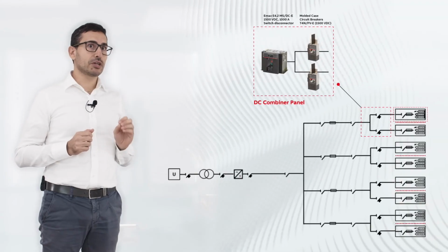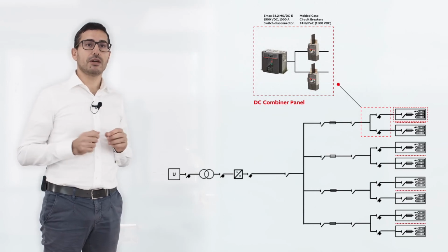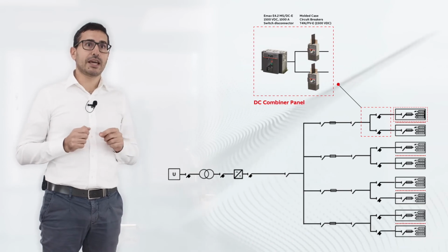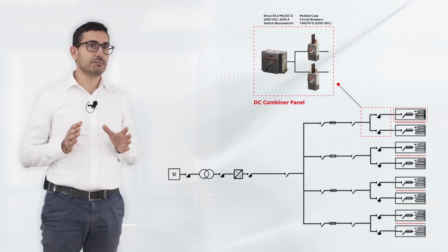Moving ahead, we can see the DC combiner panel. This is where an easy parallel connection of battery racks is provided, and very important is the protection strategy we implement for the DC combiner panel. In our case, molded case circuit breakers, T-Max T4 PV rated at 1500 volt DC are provided. They can reach up to 25 kA of breaking capacity, which is required for the application. The breakers are then coupled, and we may encounter an E-Max E4.2 switch disconnector, 1500 volt DC rated. The rated current of the E-Max 4.2 is around 1000 amps. That is one of the latest technology ABB is introducing in the market for direct current applications.